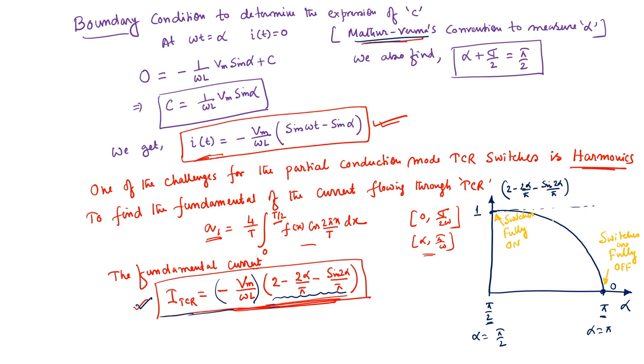This is something you need to understand. As you keep increasing the value of alpha, you are basically reducing the fundamental current of the TCR. Many times we need this partial mode of operation of the TCR when the load slowly changes from light load to full load condition. When the line is operating in light loading condition, the thyristor switches should be fully turned on, and as the load keeps increasing, the firing angle value should increase so that the amount of VAR the TCR absorbs gets reduced. That's how it works.